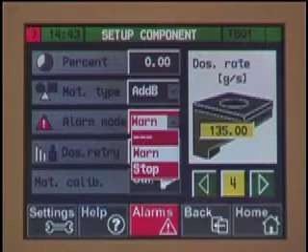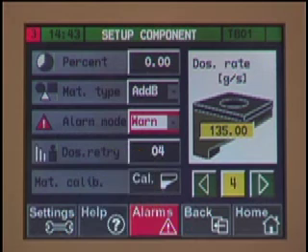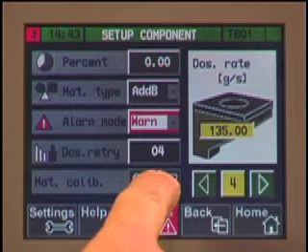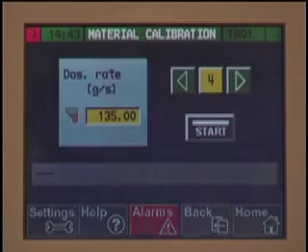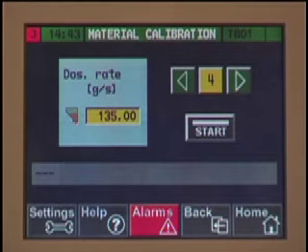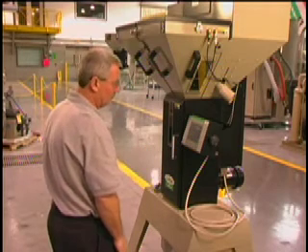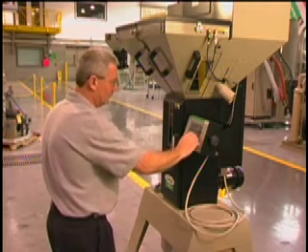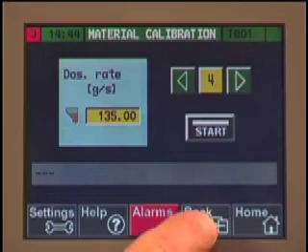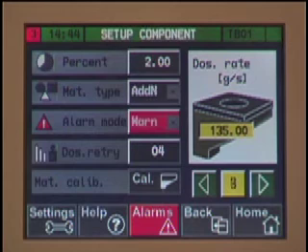Next, you can enter the alarm settings, which either triggers a warning or stops the blender if the target weight is not reached after a set number of retries. Finally, you can enter the material calibration setting, which allows the blender to reach its optimal working point more quickly. In this step, material will be dispensed from the respective position for a one-second interval and weighed, teaching the processor the flow rate of the material in grams per second. Before you start blending, be sure all bins are full.